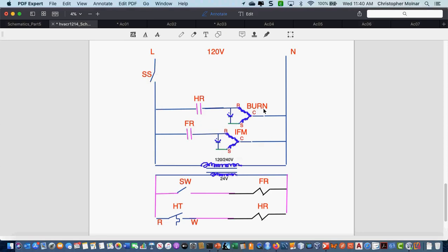Okay, yeah. Okay, again, service switch closes. In other words, we have this whole system turned on. My transformer primary is powered, which provides power on my secondary. Okay, as long as the switches are in their normal position, which they are right now, nothing runs. My room cools off under the thermostat set point. My heating thermostat closes, powers my heating relay, which closes the normally open HR and powers my burner motor.